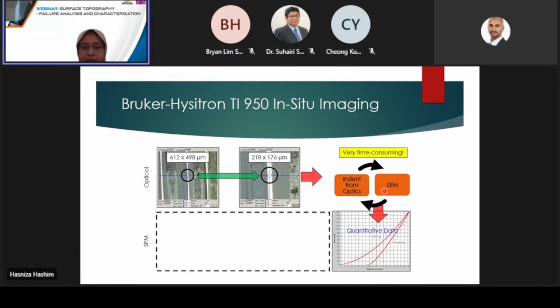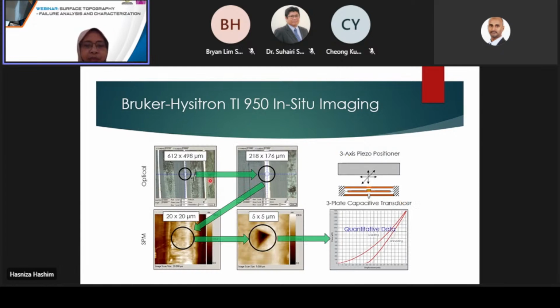So in the past, people had to go back and forth between SEM and the Nano Indenter to confirm the correct placement of very small nano indentation, which is a very time-consuming process. However, with the in-situ imaging, we can locate the area where we want to do the indentations by using the optical microscope. Then we use the SPM to do the imaging before we do the indentations. And then once we do the indentation, we can also re-image the area of indentation so that we can check the quality of indentation, whether we have done the indentation the correct way, at the correct place.